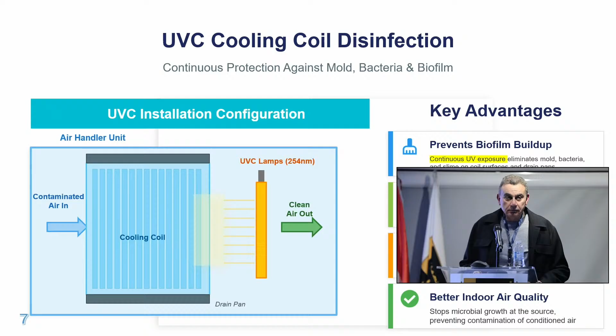Here is an example that we actually performed and tested in an actual situation. We have a huge coil, almost 4 meters wide, 2.5 meters high. We input that into the software program to select the UV light for the coil disinfection. We also input the average dose that we need in microwatt per centimeter square. These values are indicated in ASHRAE standard 185.2. It's not something arbitrary; after laboratory tests, it's proven that the average dose needs to be with this power.